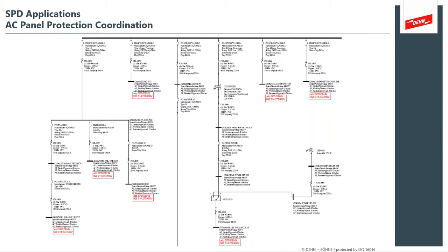You have an upstream device, you have some distance between the upstream and then the downstream surge protection devices. The standards do a really good job describing the distance to pay attention to. It's generally anything over 10 meters. We'll pay more attention to that in some upcoming slides. But this is what's really important, is to analyze your schematic, understand the voltages that are at your distribution panel. Look for things like transformers where you're stepping down into a lower voltage where you need to pay attention to separately derived neutrals and additional earthing and bonding. So again, it's about understanding your schematic and selecting the devices that are appropriate at those AC surge panels.